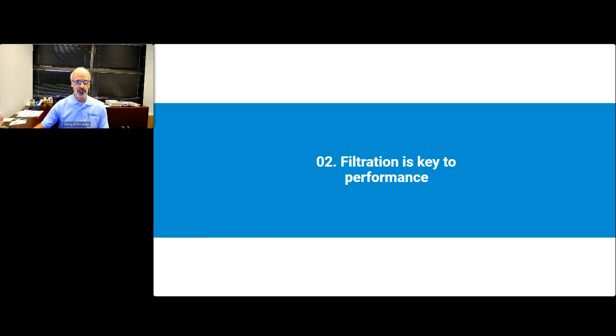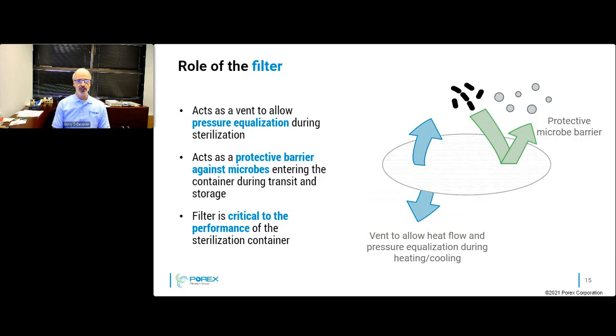So again, filtration, as I mentioned, is really key to the performance. So what is the role of the filter? The filter in a sterilization container acts as a vent to allow pressure equalization during sterilization. And what that means is, as the box is put into the autoclave, it starts off at a lower temperature and lower pressure. Once the autoclave is heated up, the pressure around the container starts to go up, which means the pressure must equalize from outside and inside, or you'll have expansion or contraction of that container, which can be a problem. So you need to allow the pressure to be equal inside and out.